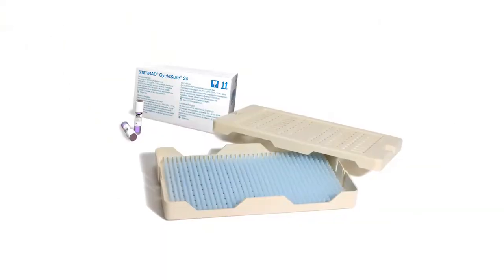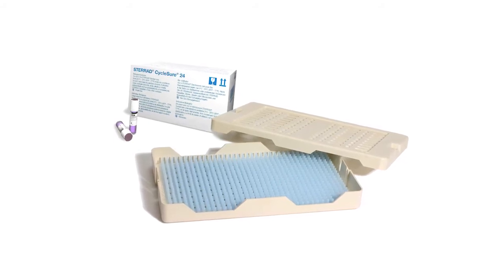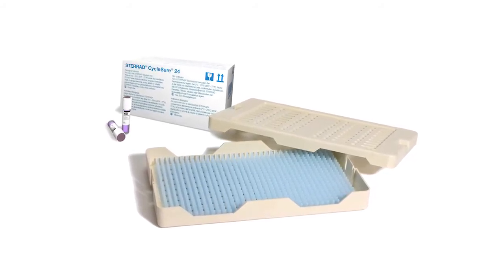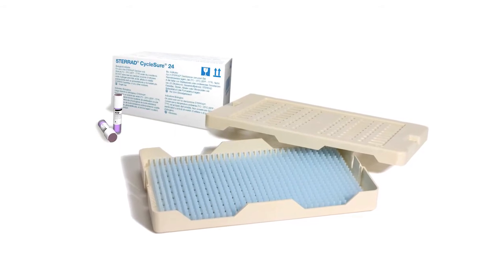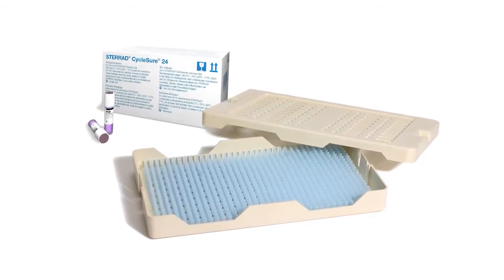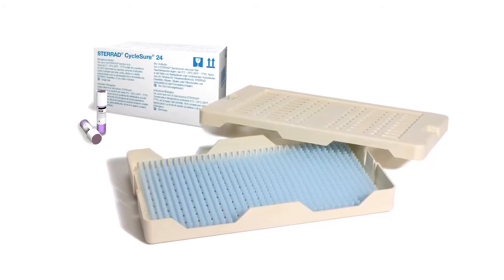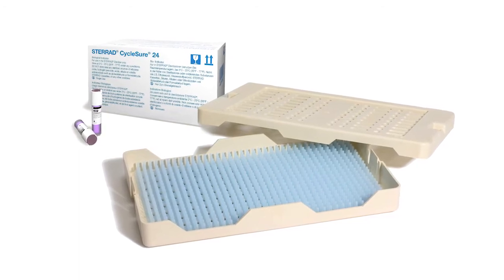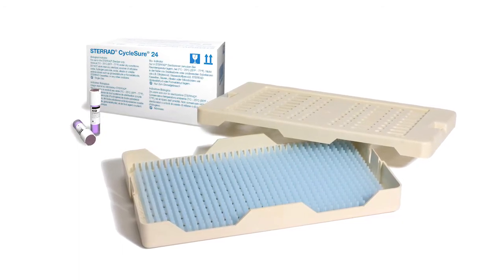Use of the STERRAD CycleSure 24 biological indicator in a test pack configuration for periodic testing confirms that a sterility assurance level of 10 to the -6 has been achieved during the cycle. Note that full instructions for use are provided in the test pack.